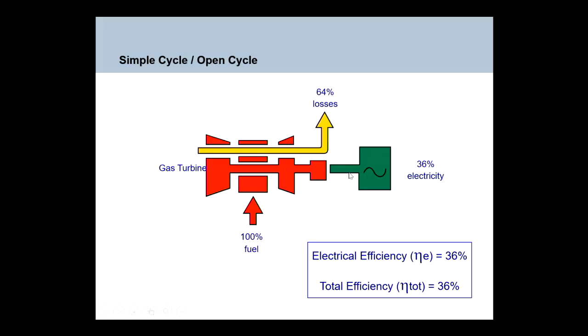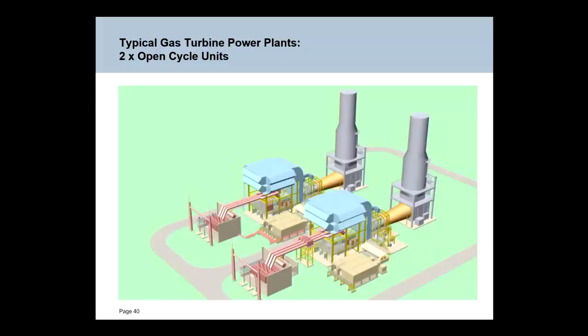Okay. And an open cycle gas turbine power plant typically looks like this. It's a 2-unit plant. You can see here, the gas turbine is here. This blue thing is the air inlet with a filter housing. So the air is drawn into this filter housing, into the compressor, and is burned with the fuel. The exhaust then comes up the stack.